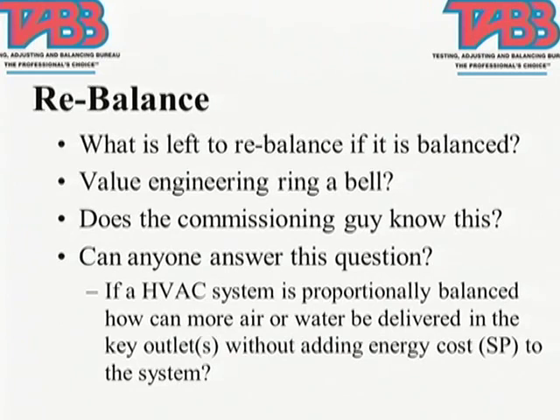So what happens is a balancer will go through the building and balance the whole building and say we have a couple bad outlets, a couple bad terminal devices. It might get thrown back at them, you need to rebalance this. Well, if they really did proportionally balance it, the only thing they can do is increase the static pressures in the system and then come back and say we need a larger pump, we need to spin the pump faster, we need to adjust the VFD so that we have a higher limit on it. And as we know, the amps go up on everything and the energy costs go up on everything.